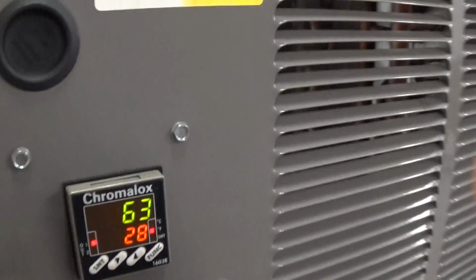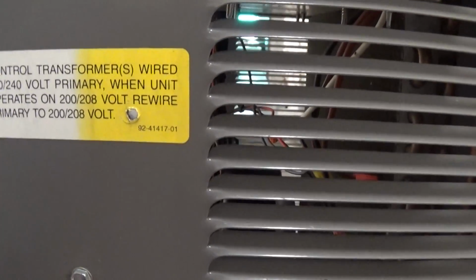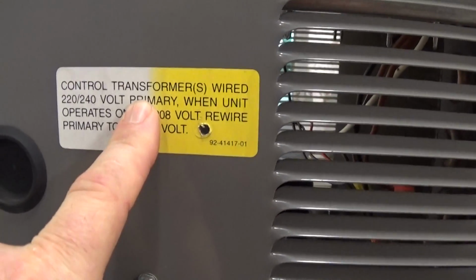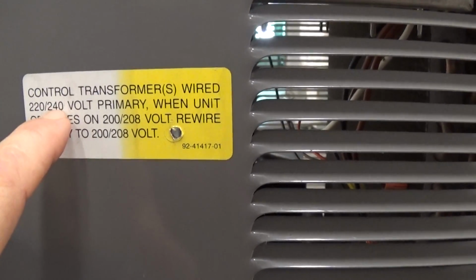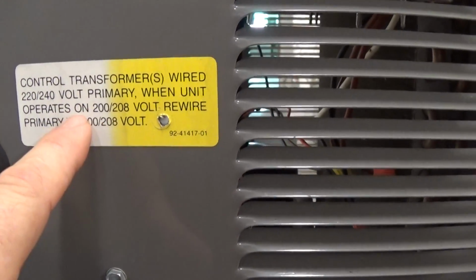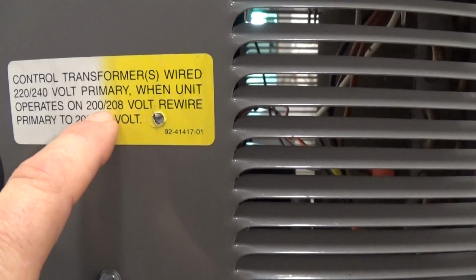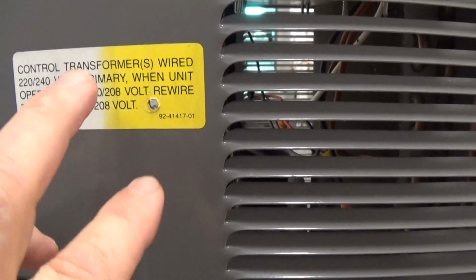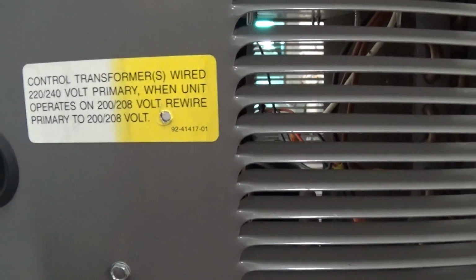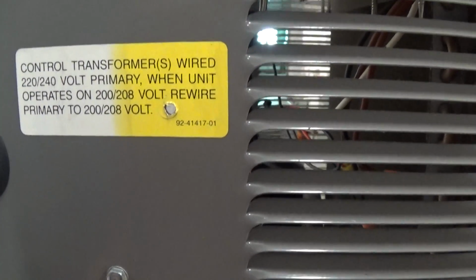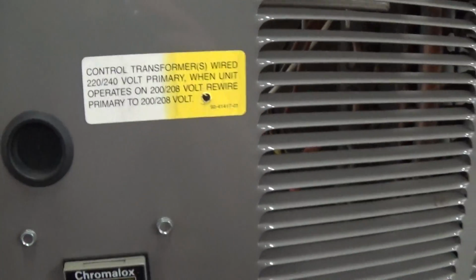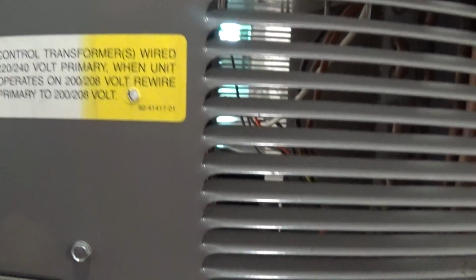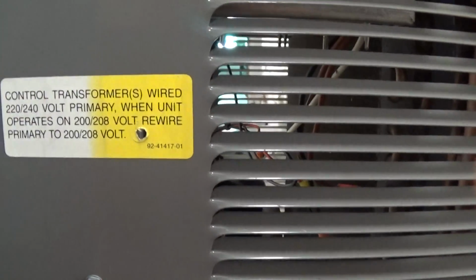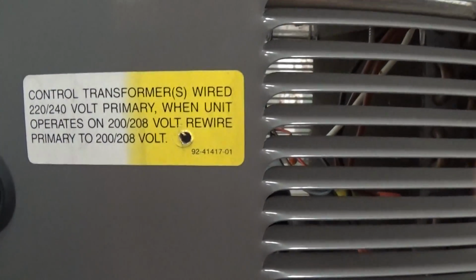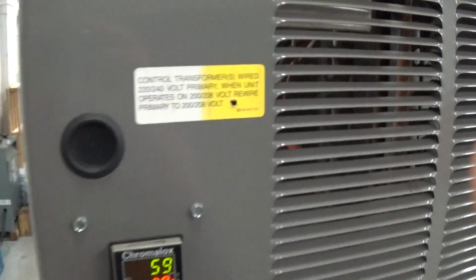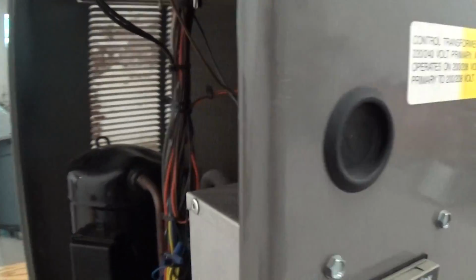Oh, depending on what voltage you're actually running, the control transformer inside is wired for 220 or 240 volts primary. If your voltage is on the low side, 200, 208 three-phase, just change the wires as labeled on the control transformer. The compressor and fans and pump are fine for either the low end or high end of the low voltage. But in the control transformer, it's nice to make that modification if needed.